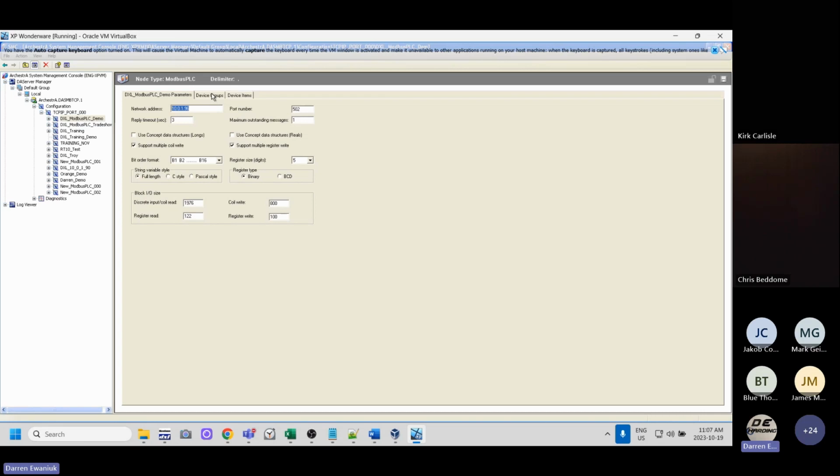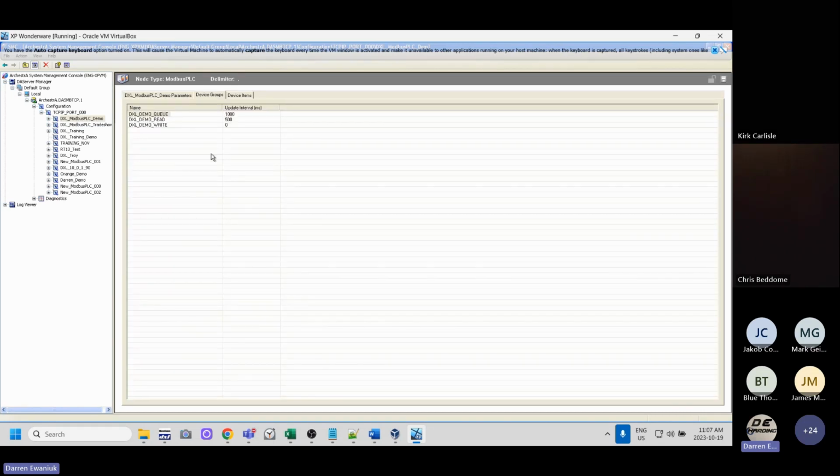Then you define the access names. These are how you would access the registers within this PLC, using these unique names. I've created 3 access names representing how often they are scanned, so each of these will be scanned at a different rate. You could do this with just a single range, but I've done this to outline that you can do scans at different rates by having different access names. The first thing I have here, so I'll start with this, is demo write.